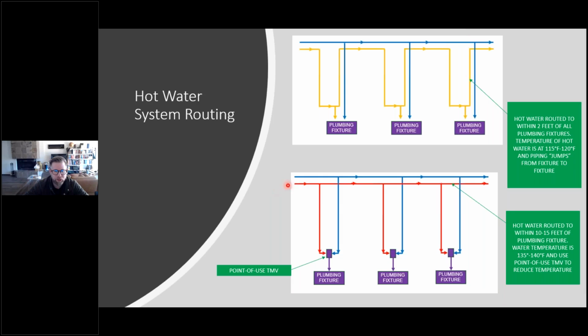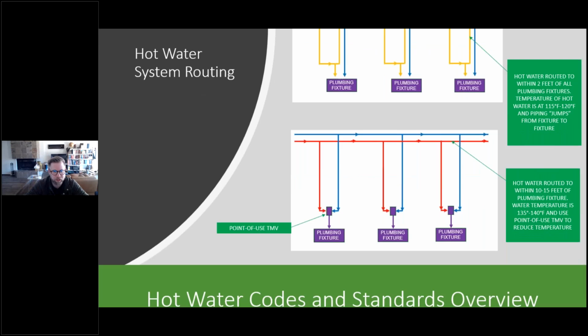You're probably going to need a little bit of a bigger recirculation pump to overcome that friction. On the flip side, if you're using an elevated delivery temperature and you're going to use your point of use TMVs to reduce the temperature, that's another approach. However, now you have an elevated temperature, and you have to recognize that if you're going over 140, you may need to slow down your velocity a little bit, just to prevent corrosion, especially on copper piping systems. Or for some plastic piping out there, once you exceed 140, the plastic derates, and some of them don't even allow usage over 140. So all these things we have to be thinking about at the same time as we're doing design of hot water recirculation systems.